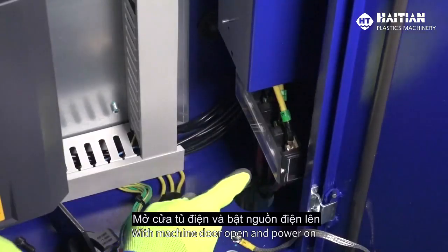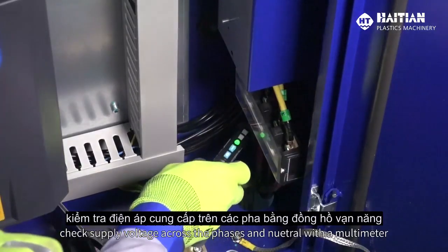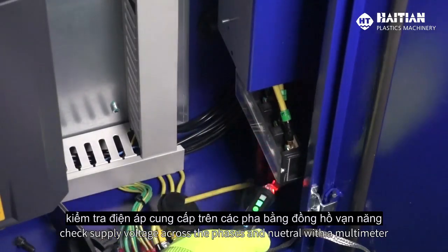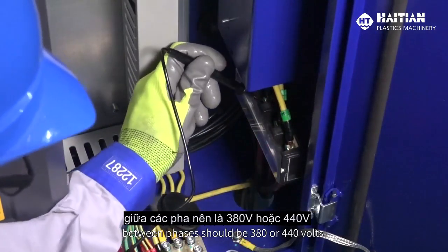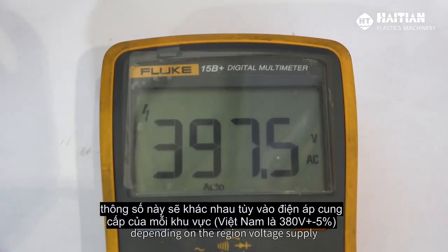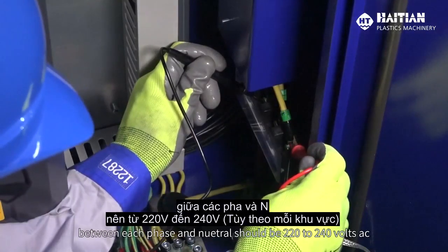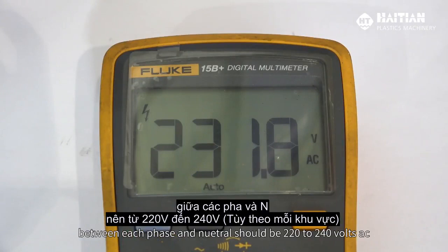With the machine door open and the power on, check the supply voltage across the phases and neutral with a multimeter. Between phases should be 380 or 440 volts depending on the region's voltage supply. Between each phase and neutral should be 220 to 240 volts.